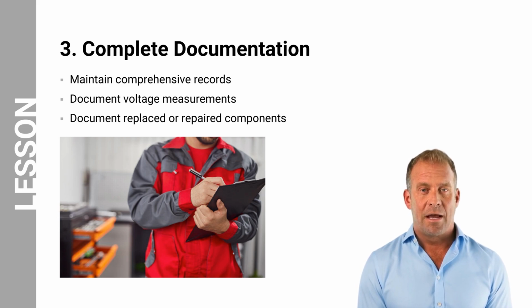Maintain comprehensive records of all work performed. Document all voltage measurements taken during the maintenance or repair work. This is vital to confirm that the high voltage system was de-energized and remained safe during the procedure. Record the adherence to safety protocols and PPE used. Keep a record of the tools and equipment used. Note any specialized equipment or insulated tools used for high voltage components.